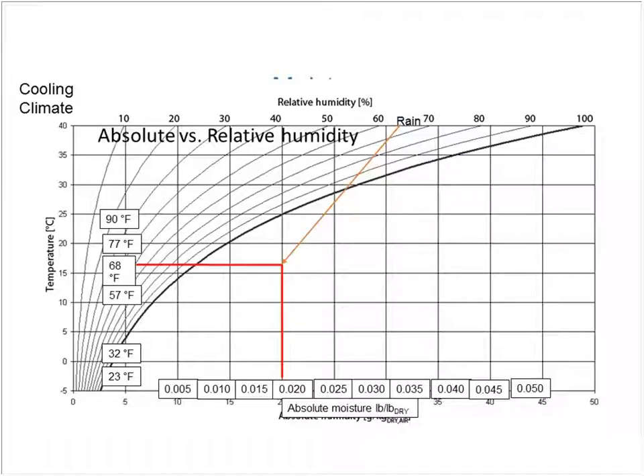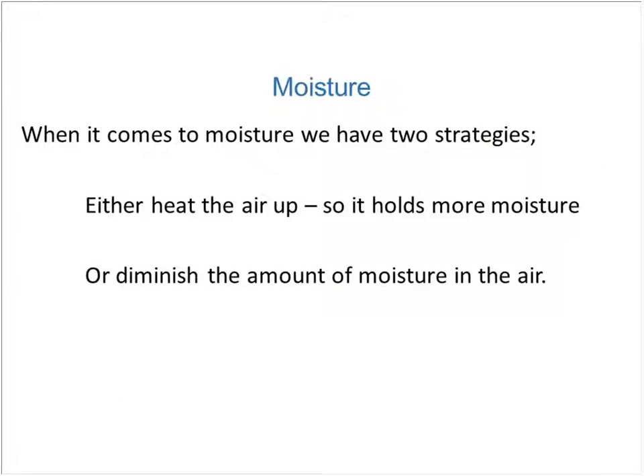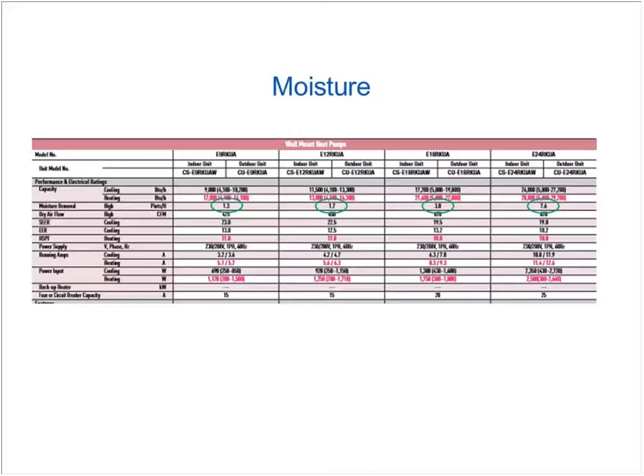So what you're going to look for in the ductless heat pump, and you're going to have to go to the manufacturer, because when it comes to moisture, there's two strategies. You either have to heat the air up so it holds more moisture, or diminish the amount of moisture in the air. So what you're going to want to go to, and this is just a copy out of our catalog here, every manufacturer's catalog will tell you the moisture removal component, and that's how many pints per hour. So in this case, a 9,000 BTU indoor head can remove 1.3 pints per hour.